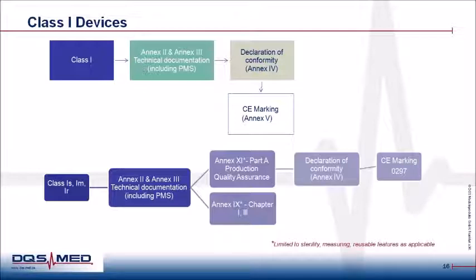So for the class 1 devices, the only route for certifying a class 1 medical device is to maintain a technical documentation in compliance with Annex 2 and 3 of the MDR. For medical devices that fall in this category, a notified body involvement is not required, and manufacturers self-declare the conformity of the device, affix the CE mark as described in Annexes 4 and 5 respectively, and thereby fulfill the general obligations of all manufacturers according to Article 10 of the MDR.